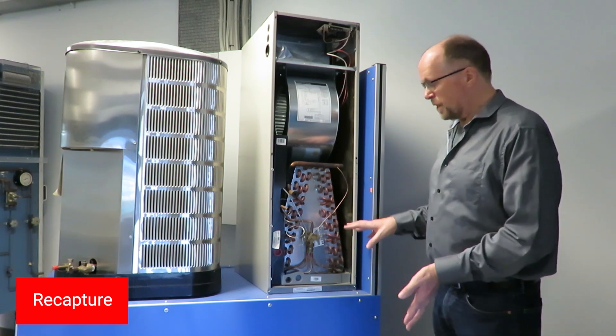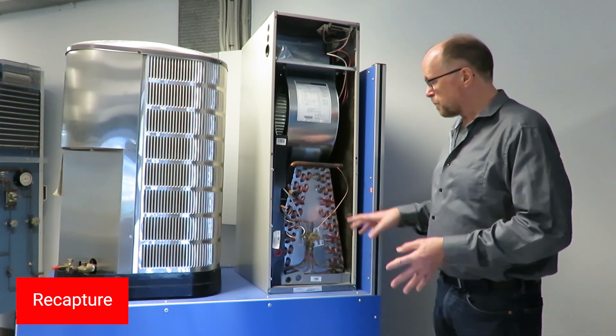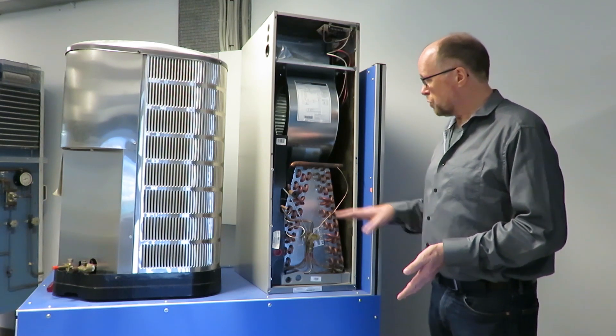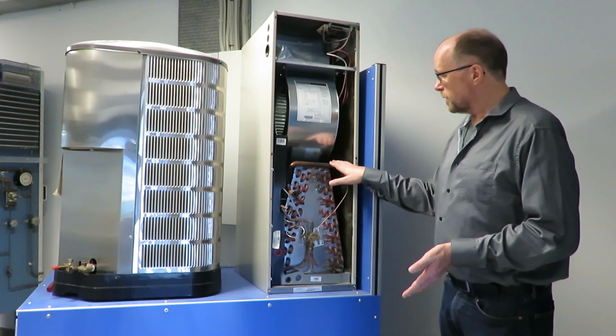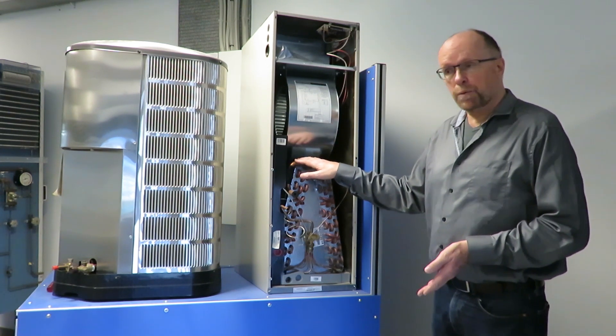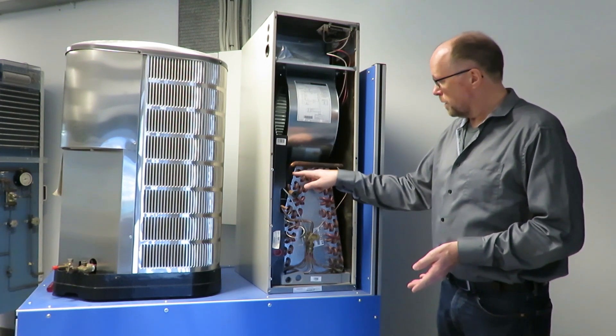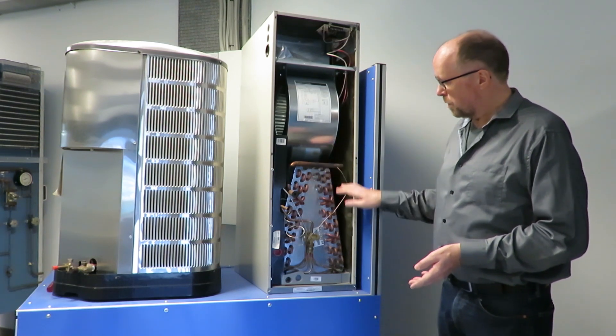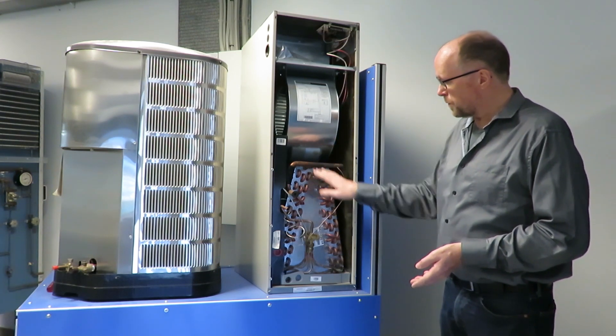The purpose of these connections is that the expansion valve is capable to see the signal or the temperature of the refrigerant that comes out of the evaporator by the bulb here. By this tube it can see the pressure of the refrigerant that comes out here.